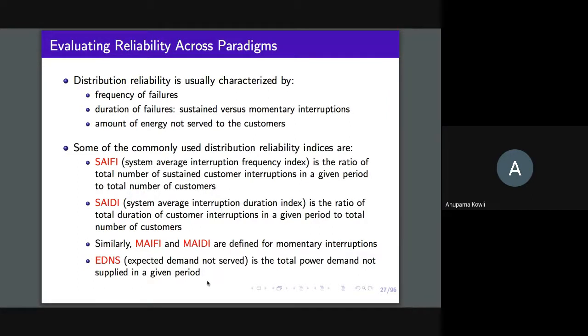These are indices that utilities are usually required to report—say every 6 months or every year, reporting how many interruptions happened and how many customers were interrupted. Interruptions are defined in two ways: a sustained interruption lasts longer than about 10 minutes, while a short interruption, less than 5 minutes, is called a momentary interruption. The frequency of interruptions, their duration, and the total demand interrupted are all used together to define indices like SAIFI, SAIDI, MAIFI, and MAIDI.